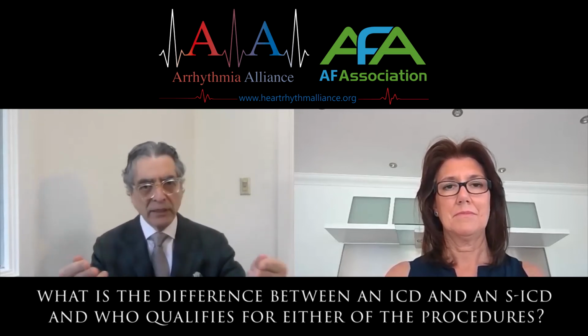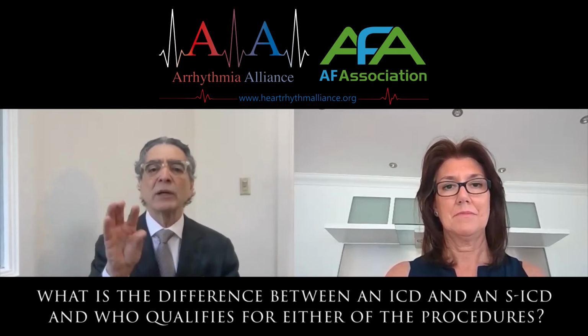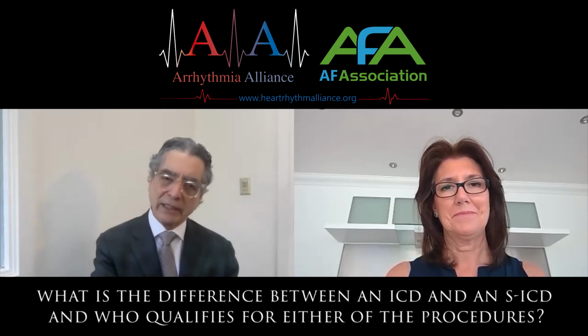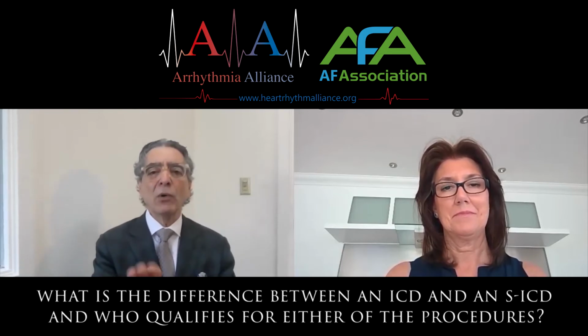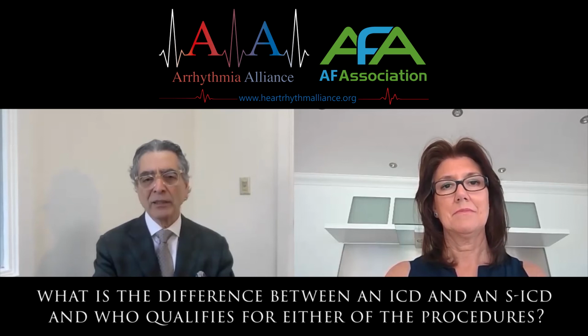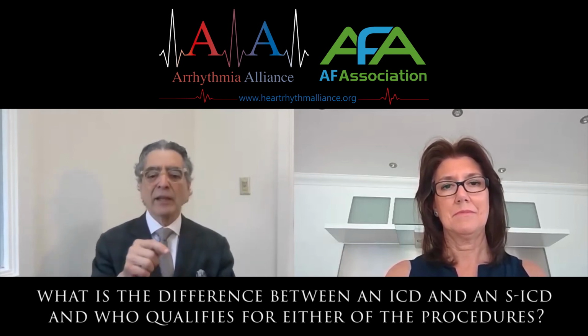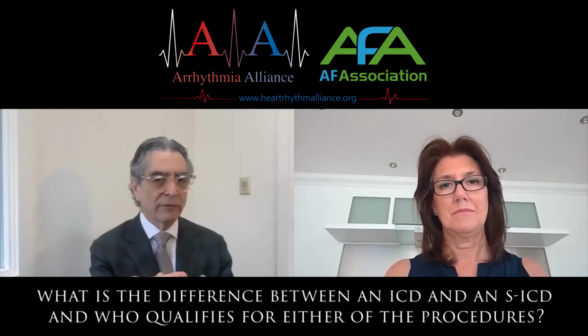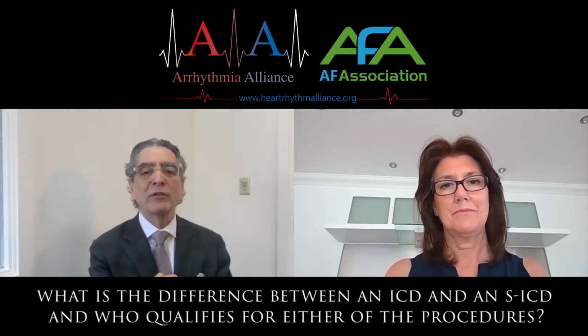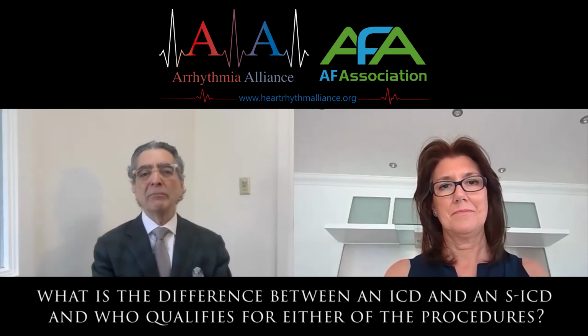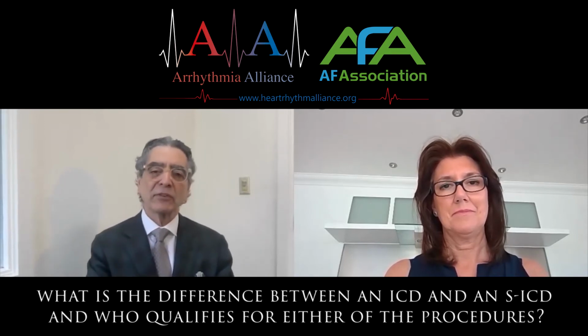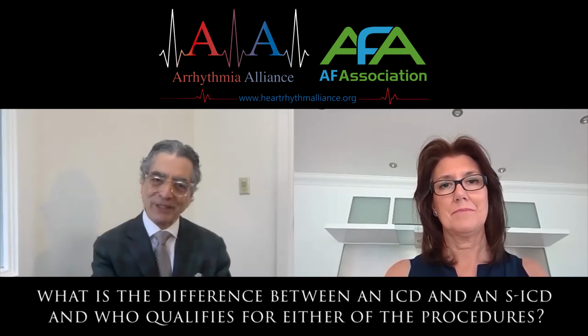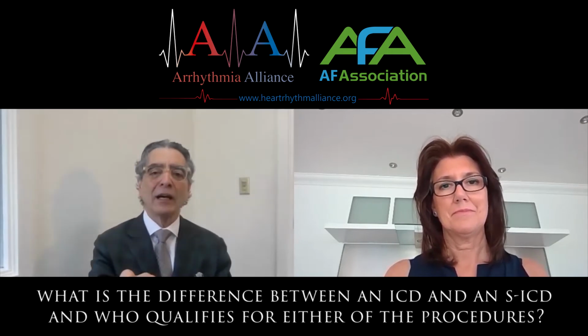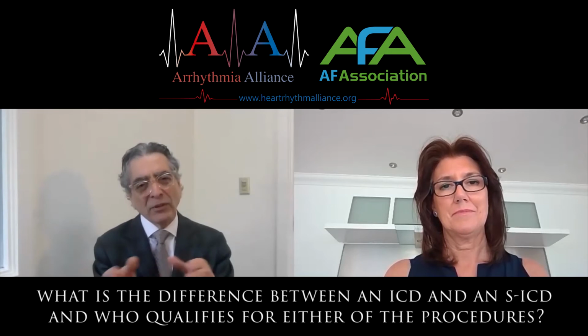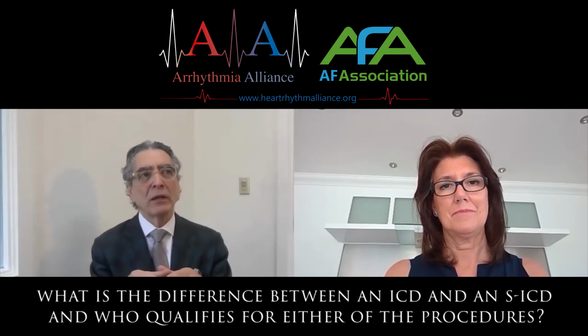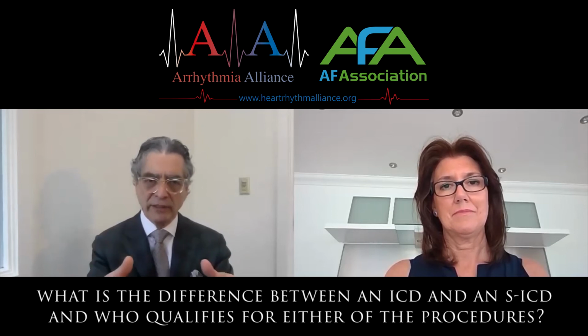There are inappropriate interventions. Sometimes they get a bit trigger happy, let's say, and they're overly aggressive, which is okay. It's not fun to be shocked, but it's okay that it is suspicious of an abnormal rhythm and overacts, rather than being, let's say, listless or lackadaisical about your rhythm. You want it to intervene aggressively. So you should expect a certain degree of what we call false positive interactions.